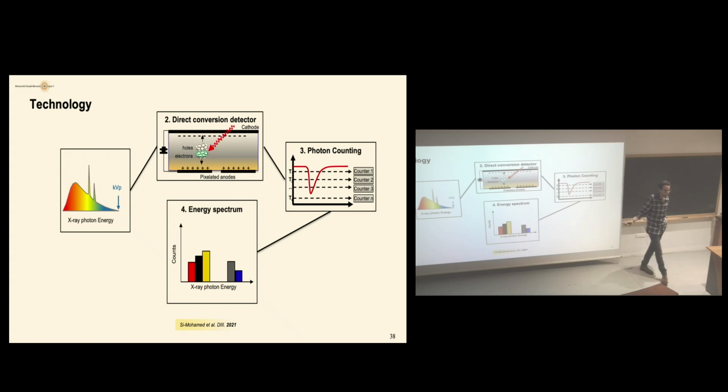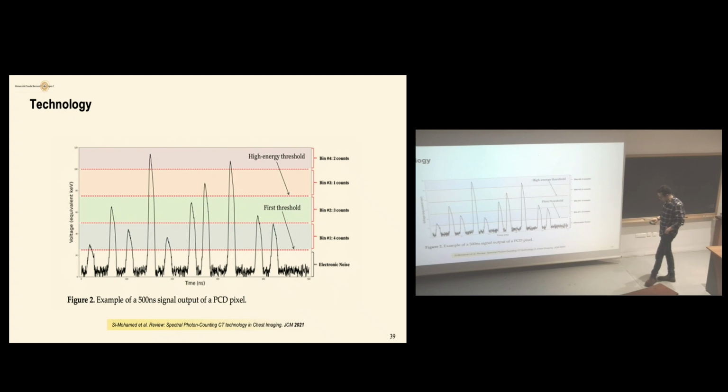And these energy windows will be the key for improving the contrast resolution. How? First, a really easy, I'll say really easy for me to understand, but a really nice aspect. This is the fact that these bins will allow to classify the really low energies below 30 keV, which will correspond to the electronic noise.